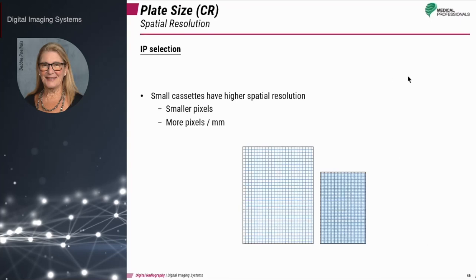Spatial resolution also depends on imaging plate size. CR readers scan at a relatively constant frequency of about 2,000×2,000 pixels. Using the smallest imaging plate possible results in the highest sampling frequency and thus higher spatial resolution. Smaller cassettes have higher spatial resolution because they have smaller pixels and therefore more pixels per millimeter.